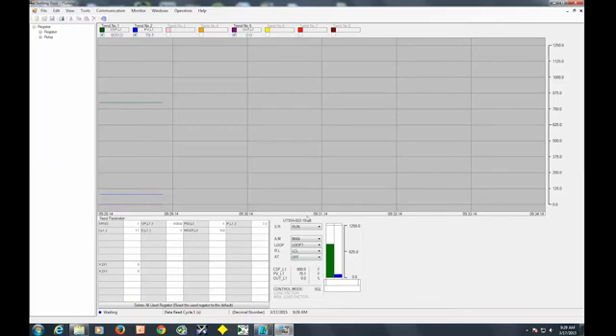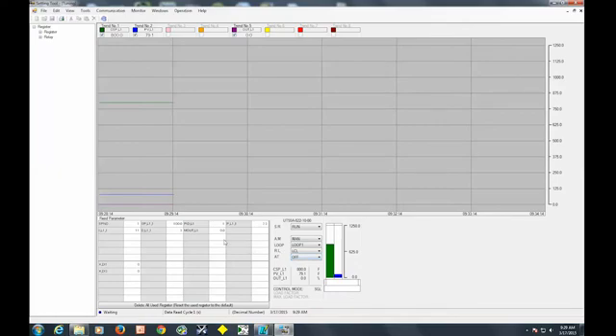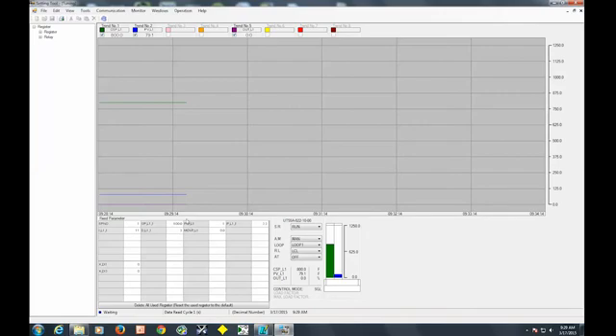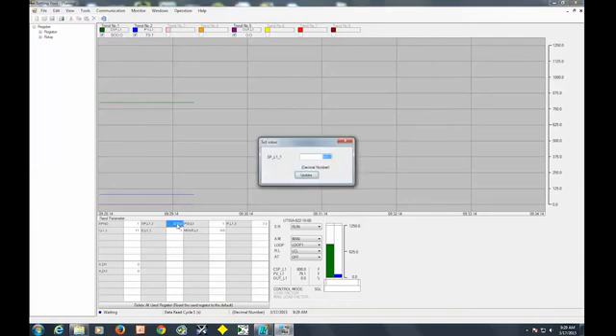These are our mode settings here. We can actually put the controller in auto or manual. We can put it in auto-tune or turn auto-tune off. We can change set points over here. What we're going to do now is when you go to do your auto-tune, make sure your desired set point is entered. I'm going to use 800, but to make a change, you would just double click on the value, make your change here, and then click update. And you'll see the set point change on the controller face.